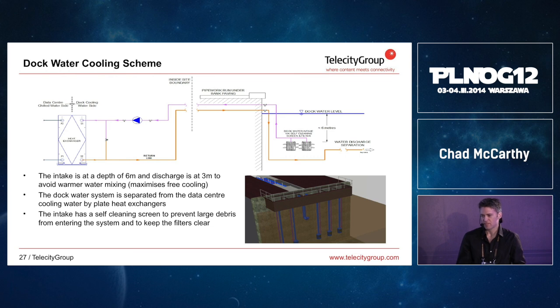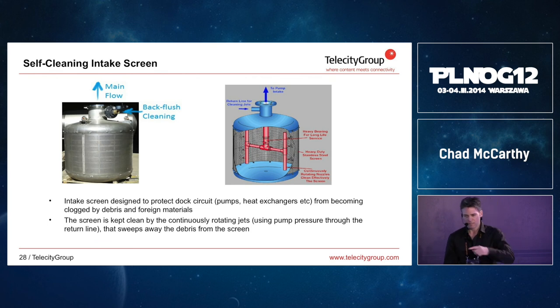The intake itself has a self-cleaning screen. You can imagine that this isn't clean water, it's very salty, it does have a certain amount of particles in it. And the way that works is we have this permanently rotating cleaning mechanism. There's water being forced out of the intake nozzle, which on the right-hand side you can see the red pipe work, which is rotating, and that effectively cleans via a pressure wave the filter mesh, and that's rotating around constantly. And where these two blades are not cleaning the mesh, we have an intake of water at a perpendicular angle. And so this is how we avoid clogging and constant cleaning of these filters. It's quite a clever system.